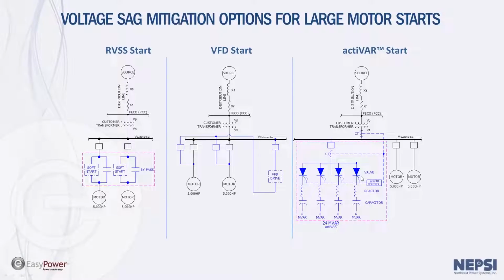The third option to the right here is the actiVAR. This is the product offering that we're talking about. It is a capacitor assisted motor start. In this situation, we've had four 6 megavar cap banks that are thyristor switched to supply reactive power to these motors during starting. So you can see that this is a shunt connected device. We're connected straight to the customer bus. There are no interposing breakers, no additional breakers required. When the motor starts, the CT here will sense the reactive power flow, and these thyristors will gate on to conduct reactive power locally to the motors.